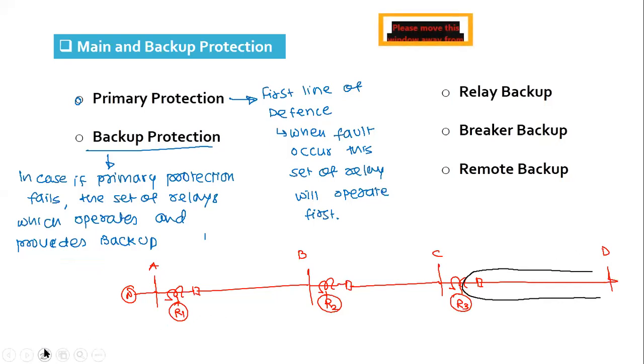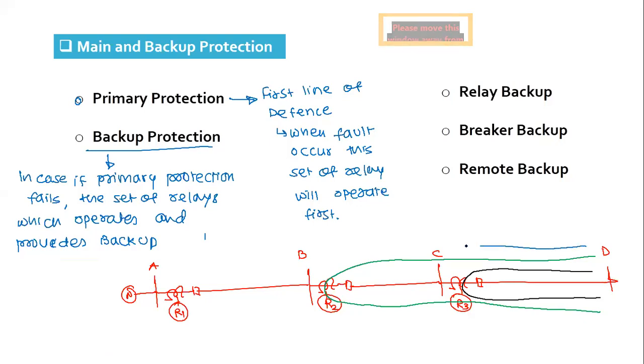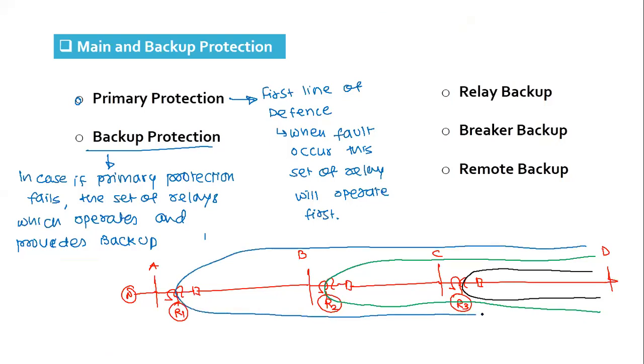This relay reach we are going to set from, let's say, B to D, but with higher operating time. And the third relay, we set the reach of relay R1 from, let's say, A to D, like this. Okay. Reach is the remote limit of the zone of protection from where it will operate. Suppose I have placed a relay at substation A, then what is the remote limit? It will operate for any fault up to substation D. That is what is called the reach of the relay.